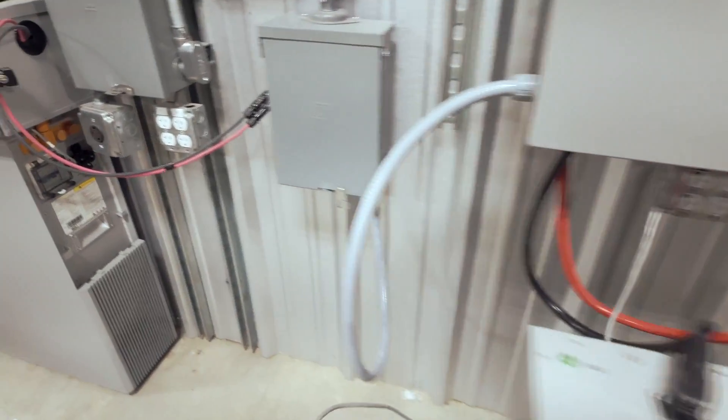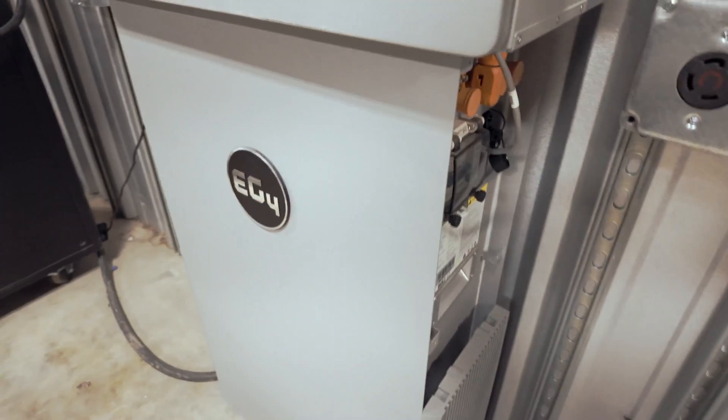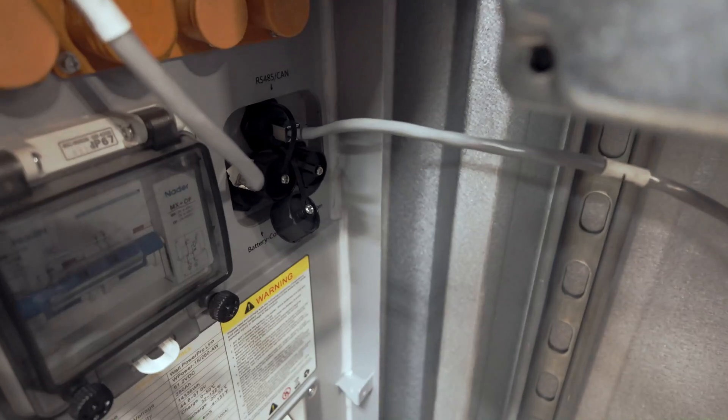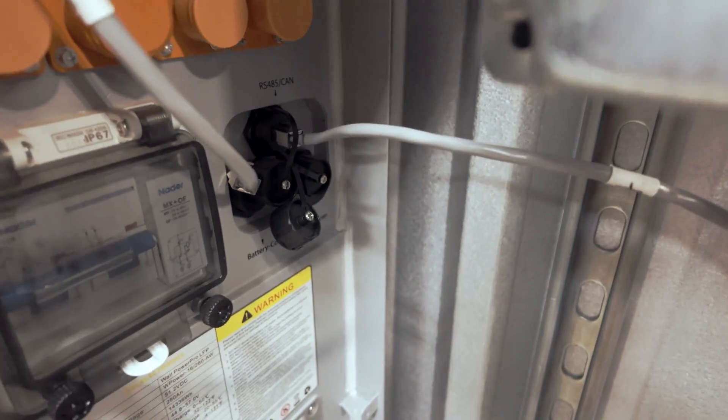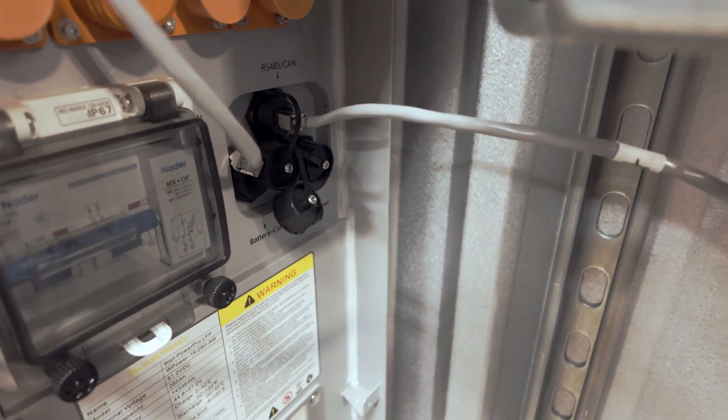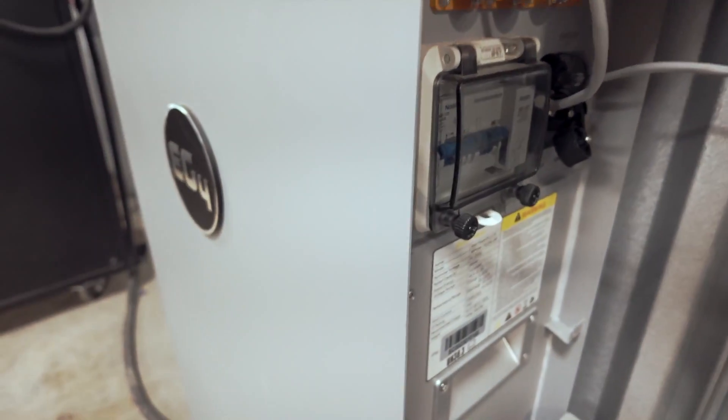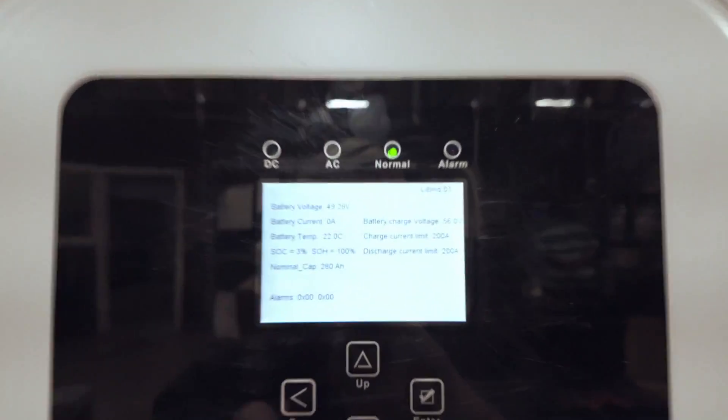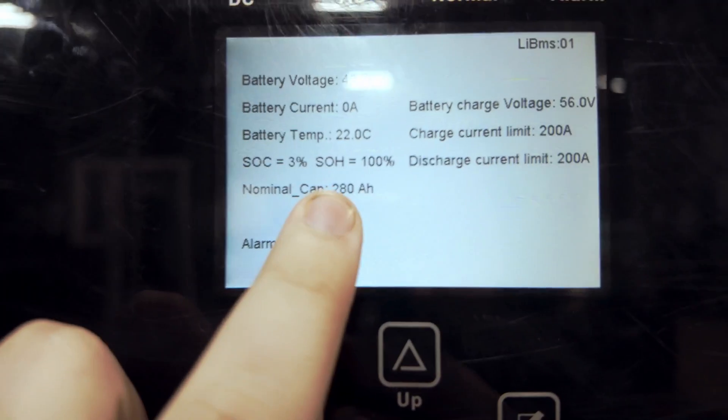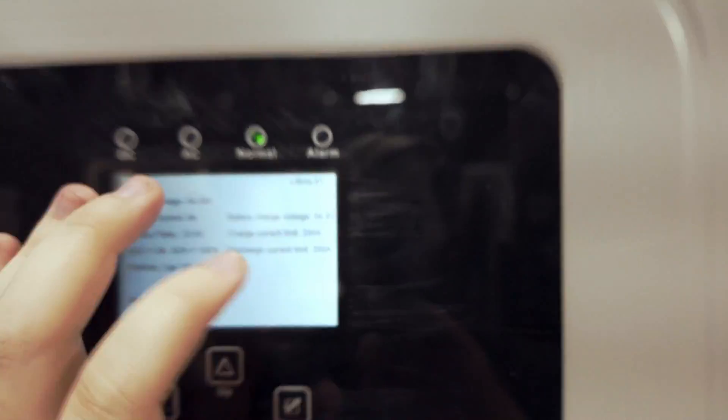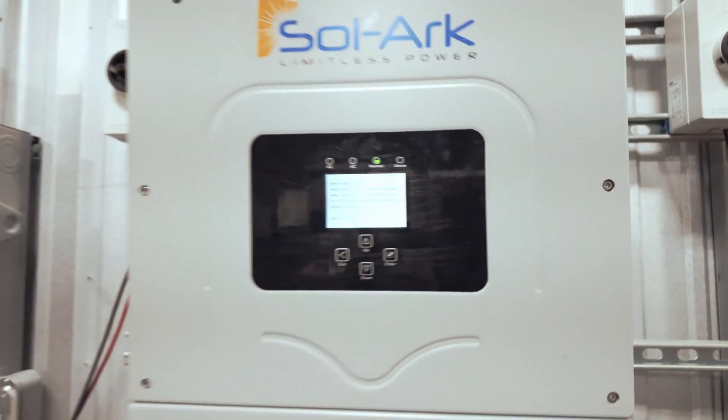Communication also works pretty seamlessly with the outdoor wall mount battery. Simply slot it into the RS-485 slash communication or CAN communication port. Set your protocol to Sol-Ark similar to the way we did it with our indoor wall mount. And you'll see on here it has the same parameters. We got 280 amp hours and then of course 200, 200 for charge and discharge.